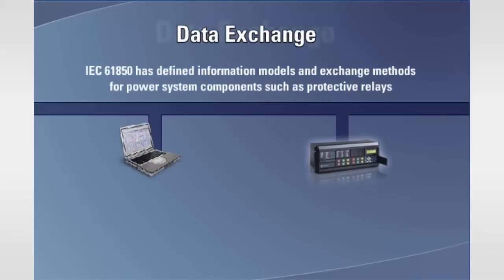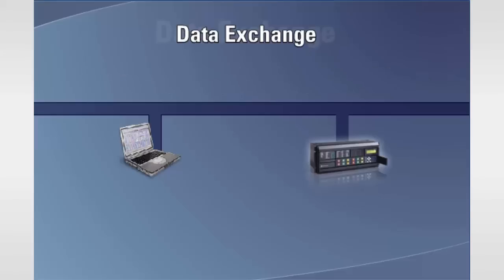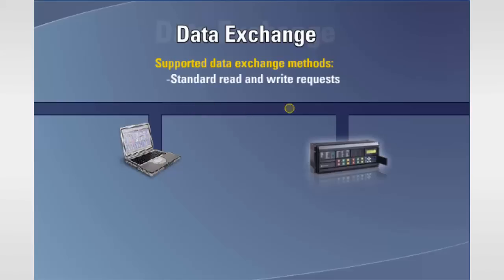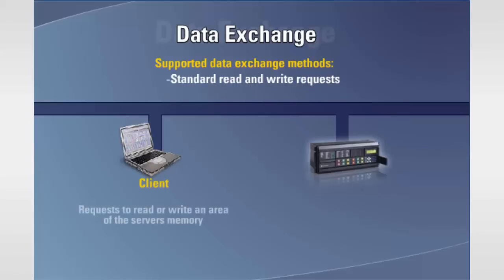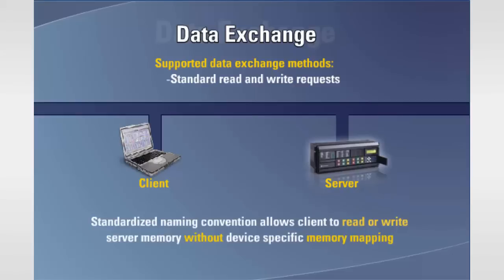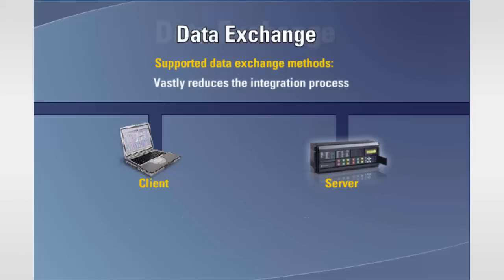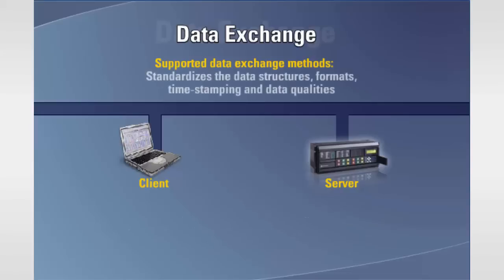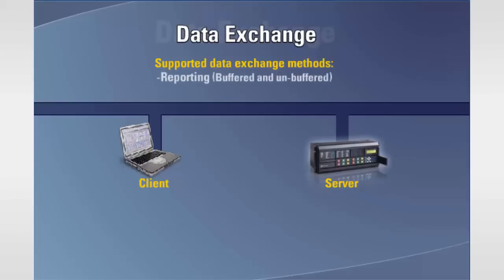IEC 61850 has defined the information models and exchange methods for power system components such as protective relays. Within IEC 61850, the supported data exchange methods include standard read and write requests, in addition to buffered and unbuffered reports. With read and write requests, the client requests to read or write an area of the server's memory, and the server responds. Within IEC 61850, a standardized naming convention allows the client to read or write server memory without device-specific memory mapping, vastly reducing the integration process. This protocol also standardizes the data structures, formats, time stamping, and data qualities. The second data exchange method is known as reporting, which is ideal for sampled value distribution, historical data, sequence of event logs, and control devices.